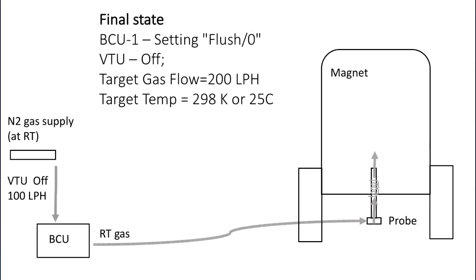Now we can attach the nitrogen gas supply to the BCU. We need to set the target gas flow to 200 liters per hour and target temperature to 298 Kelvin, or 25 degrees C, for the next user.